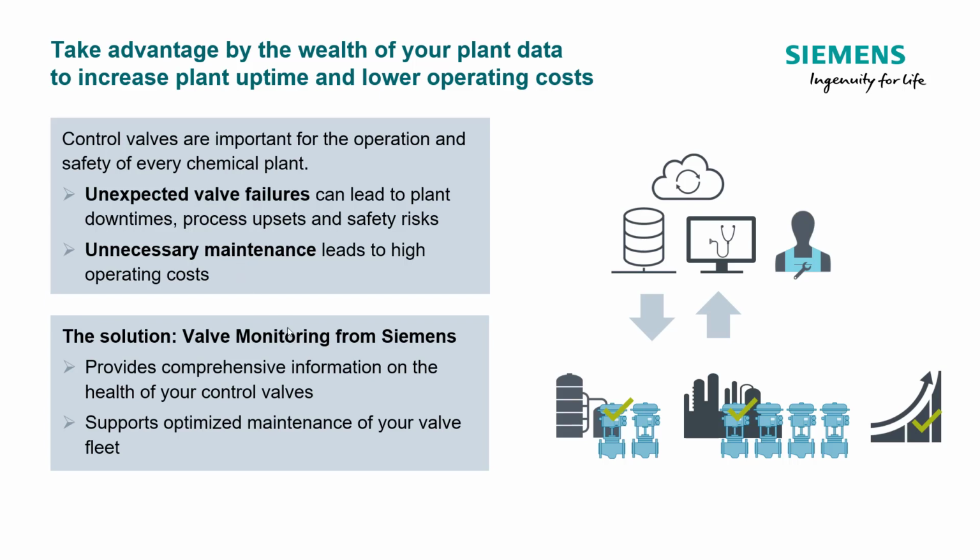So this is where we can push the data off to the cloud. The data is constantly being recorded and measured by the valve positioner, so it's not something we do once every 6 months and then analyze the results. It's happening all the time, every day. If you've got a steady state valve, then we can do things like partial stroke tests and analyze that data. But really, this is for control and modulating valves.